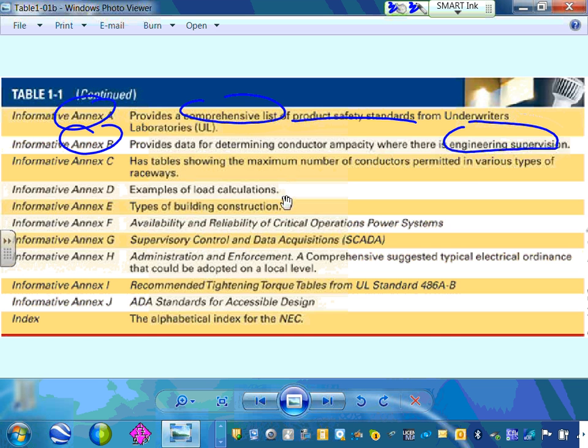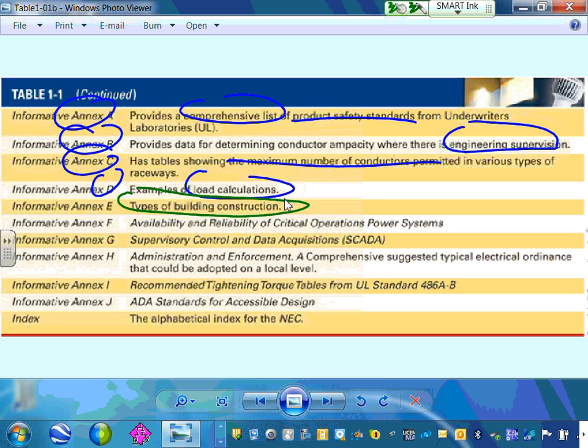The other annex shows the maximum number of conductors. This is very important—it tells you how many conductors you can fit in a conduit if they're all the same size. There's also an example for load calculation. These are really cool; it shows you how to do a load calc.